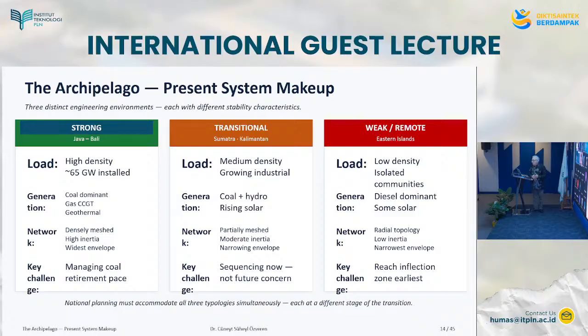If you look at the swing equation, the rate of change of frequency is proportional to delta P. So the island will see 25 times the rate of change of frequency fall of the Java Bali example, right? So the same amount of generation loss will cause a bigger drop in the outer islands than it will in the Java Bali system.